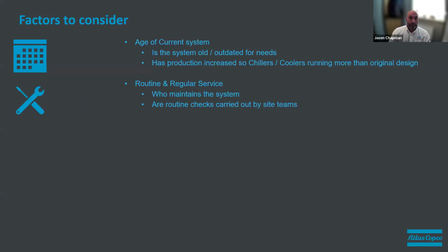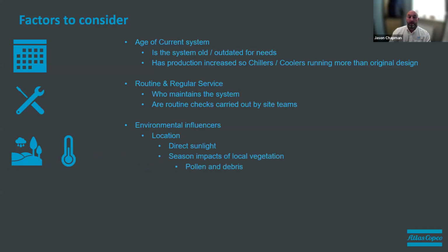Other things to consider then. A common one for us in this country is the environmental factors. Now, we are only a small country, but throughout this country we've got various degrees of weather and environmental impacts. So location makes a big direct impact on your chiller performance. Not just where they are in the country, but where are they based on site? Are they in direct sunlight? With that in mind, we also have to think about the seasonal impacts, local vegetation, pollen and debris. Are you next to a road? Are you next to a recycling plant or something like that? All these types of things need to be considered, especially at this time of year, when we get lots of tree pollen and things like that. These can all have a real detrimental impact on your chiller and cooler system, as they can on compressed air as well, by clogging up your coolers.